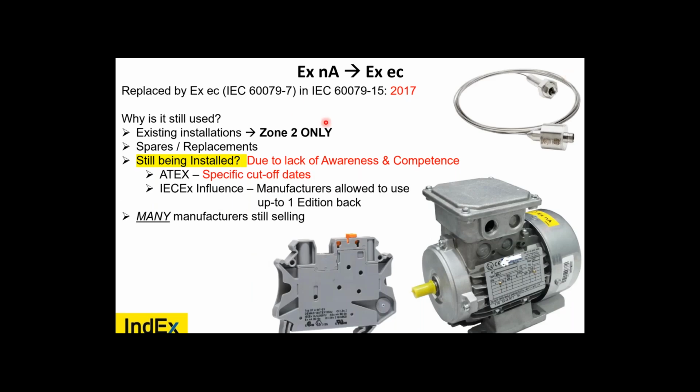So what's going on with EXNA? Well, in 2017, it was upgraded, I would say it's an upgrade, to EXEC. Why is it still used? Well, existing installations of Zone 2. Spares and replacements. Why is it still being used? Due to lack of awareness and competence.